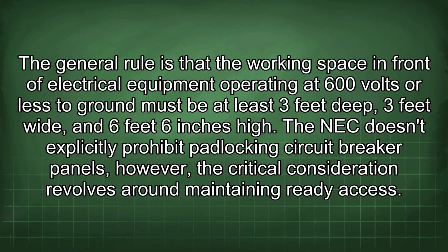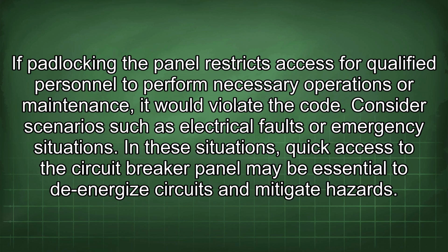The NEC doesn't explicitly prohibit padlocking circuit breaker panels, however, the critical consideration revolves around maintaining ready access. If padlocking the panel restricts access for qualified personnel to perform necessary operations or maintenance, it would violate the code.